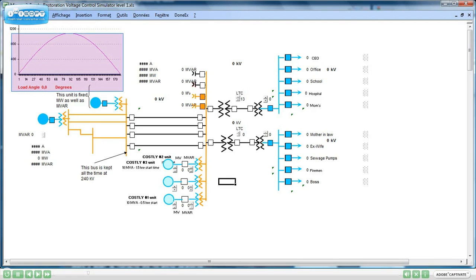On top left, there is a print of the original load angle before the blackout. There are two power plants in service. The first one is set at 0% speed droop, so the users will not have to take care of the frequency. With this power plant, users will be able to manually increase the megavars output of the unit. There are 4 long lines with huge Ferranti effect, and 4 cap banks that are controlled with breakers.